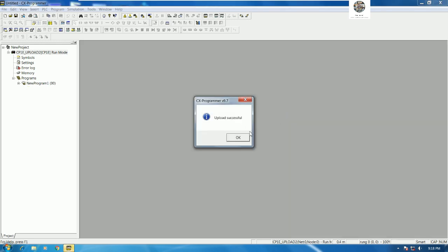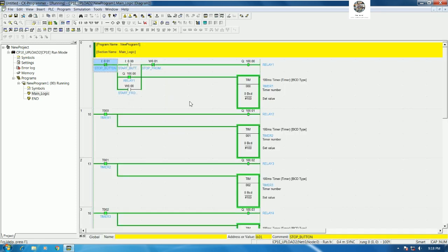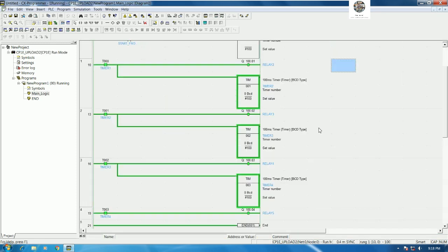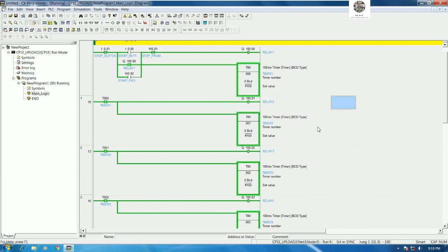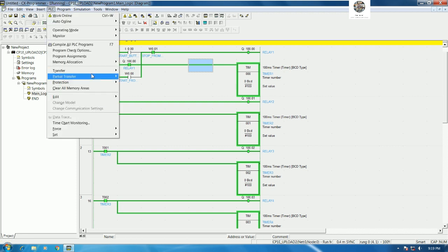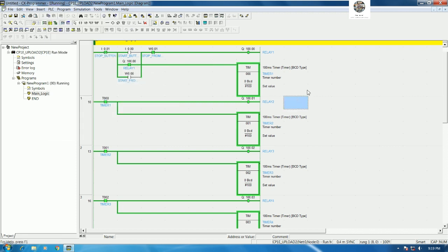Then we can go to the main program and then double click here, we will get the program also. So there are two ways for uploading the program from PLC Omron. The first we can use the direct online automatic search and then upload. The second way we can create a project and then choose the hardware the same as the real PLC, and then we can online and then transfer from PLC to PC.